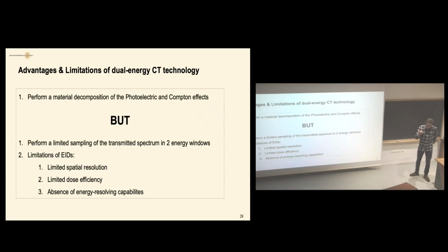Anyway, with energy integrated detectors, you can perform a material decomposition of the photoelectric and Compton effects, as we saw with dual energy CT. You use two different X-ray spectra, decompose, and use the Alvarez and Macovski equations to calculate the photoelectric and Compton effects. But, and this is important, you cannot perform more than 2 energy windows sampling of the transmitted spectrum, which is a real limitation for expanding the material decomposition process, and that will be the interest of K-edge imaging later.